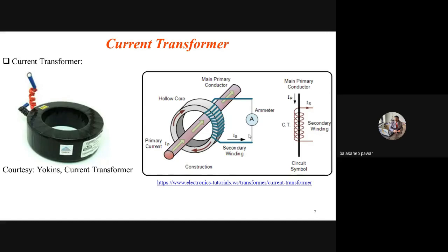So simply you have to do the reverse calculation. The measured voltage, that is the voltage drop across that 1 ohm resistor, is 500 milli. That means the current flowing through that 1 ohm resistor is how much? I equals V by R. V is 500 millivolt divided by 1 ohm. Your answer will be 500 milliampere. That's all. Are you getting it? So simply by using a voltmeter, you can measure the current flowing through the current transformer, CT, by using this simple trick. Just connect one small resistor. Now again, one more thing which is most important: why am I saying a small resistor across the secondary?